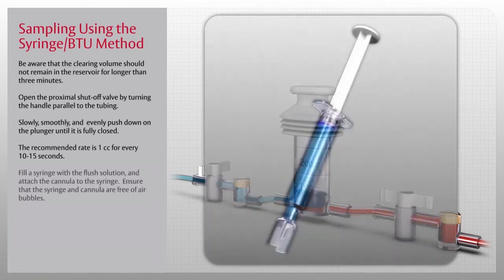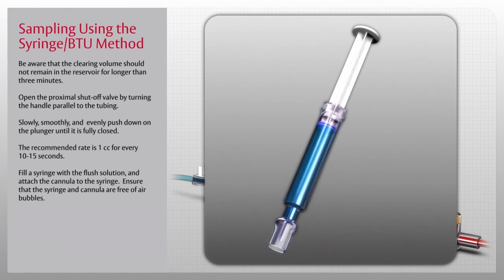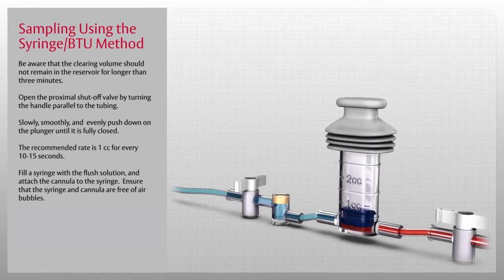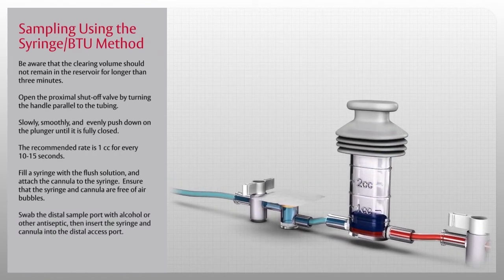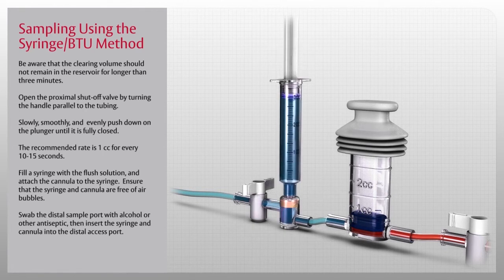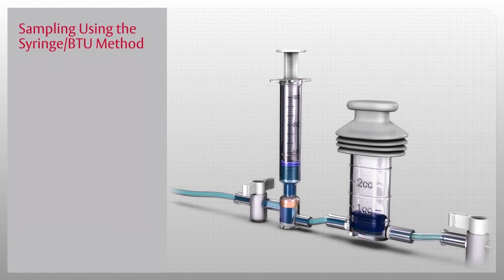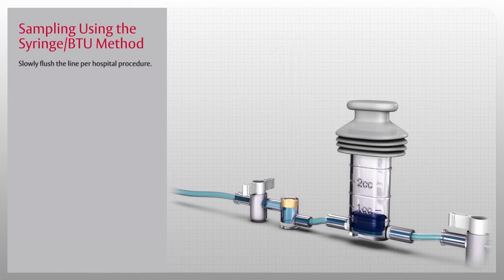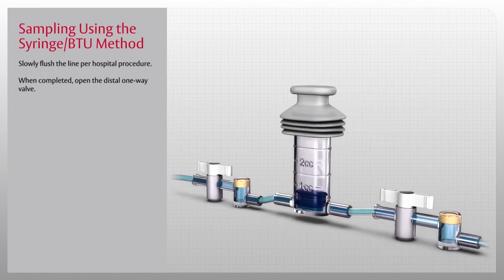Next, fill a syringe with a flush solution and attach the cannula to the syringe. Ensure that the syringe and cannula are free of air bubbles. Swab the distal sample port with alcohol or other antiseptic, then insert the syringe and cannula into the distal access port. Slowly flush the line per hospital procedure. When completed, open the distal one-way valve. Note, the approximate volume required to flush the line is 1 to 1.5 cc's.